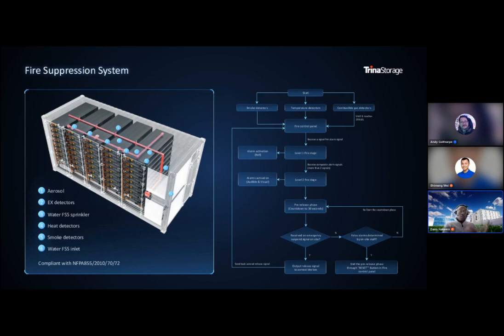So we've got smoke, heat, and gas detectors that would all trigger depending on whether their thresholds are met - excessive heat, smoke, or gas detection. Then the Elementa triggers the BMS actions, such as opening vents to release gases, or in the worst case, triggering a level 2 shutdown of the system.